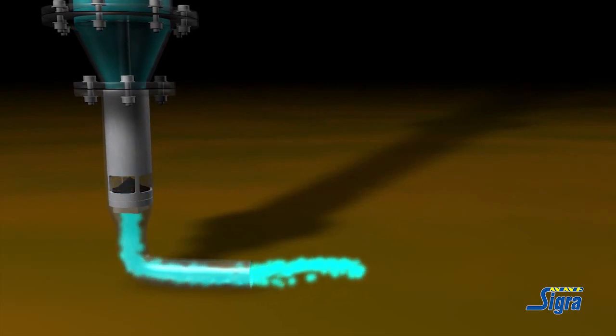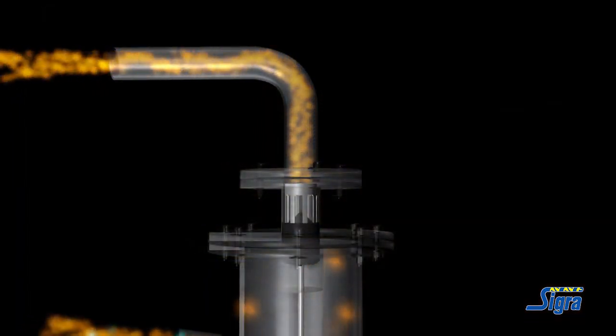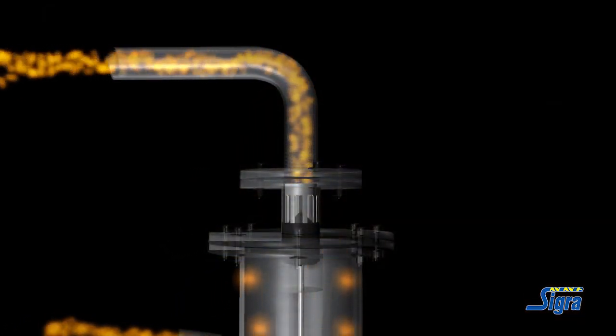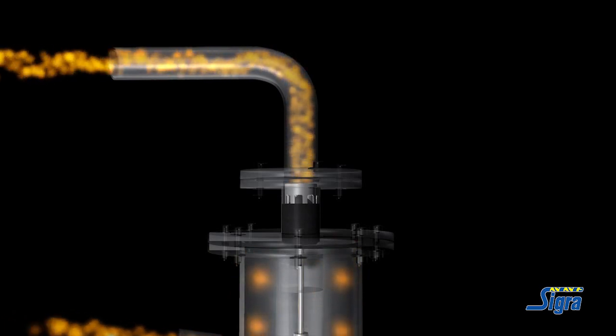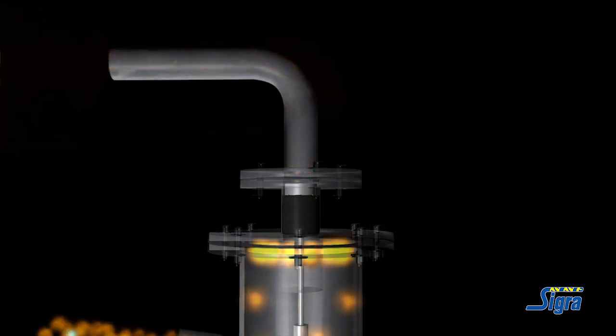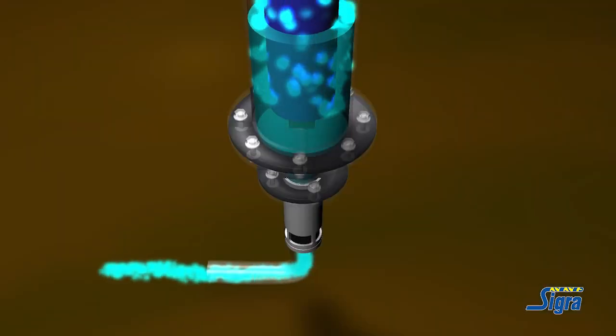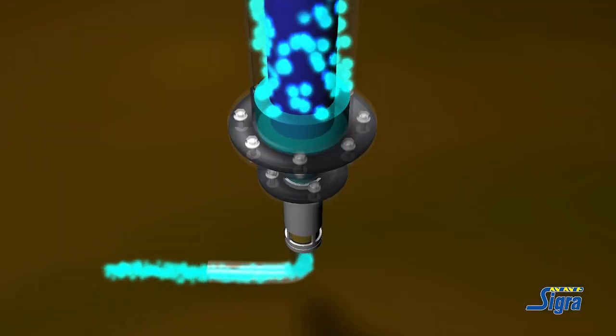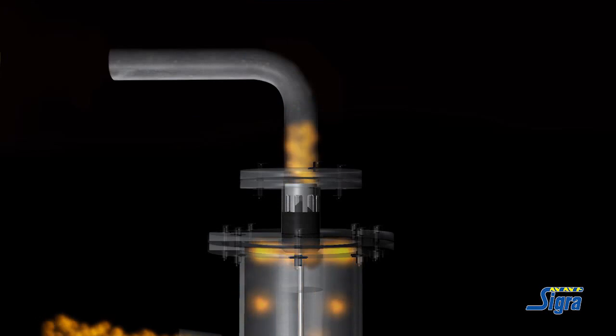The liquid valve shuts if the liquid level in the separator reaches a low level so as to prevent the loss of gas into the liquid takeoff. The gas valve is fully open when the liquid valve is shut, but if the liquid level in the separator reaches a high level, it closes so as to prevent the entry of liquid into the gas line and enables liquid to be purged from the separator before reopening the gas valve.